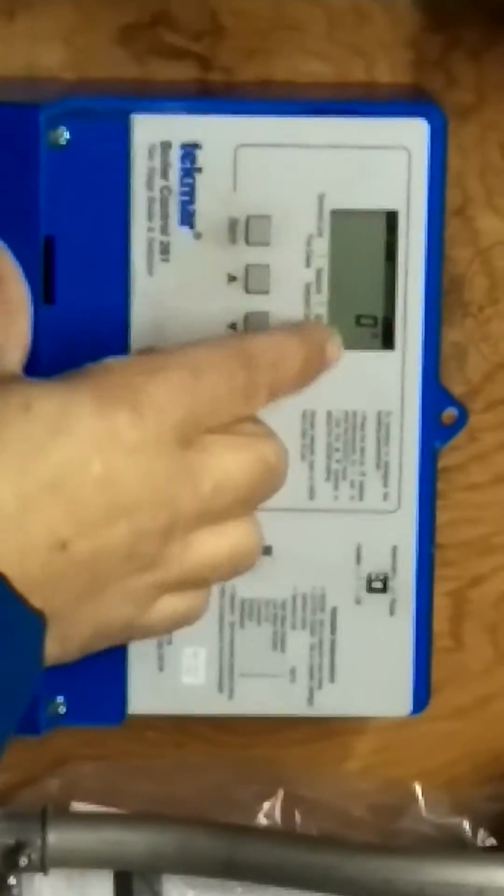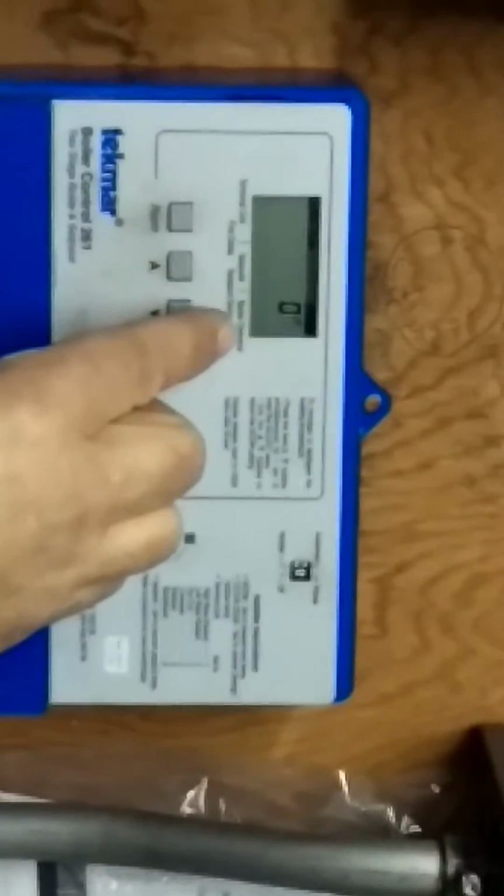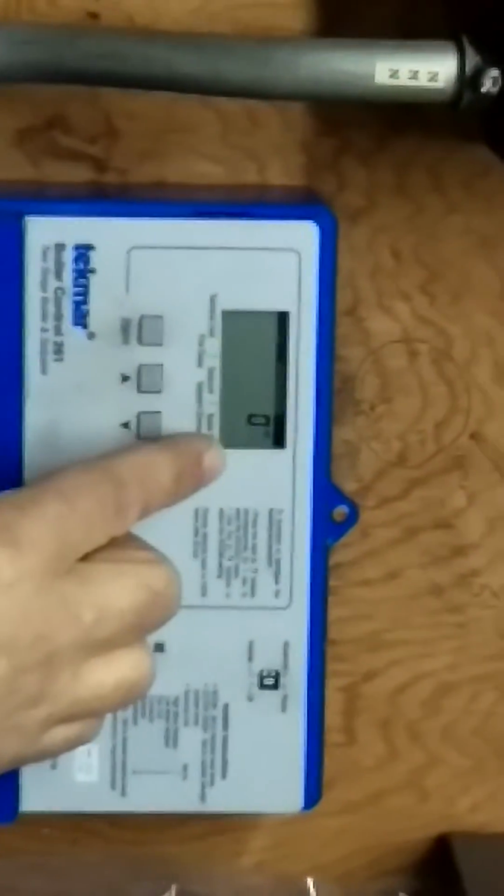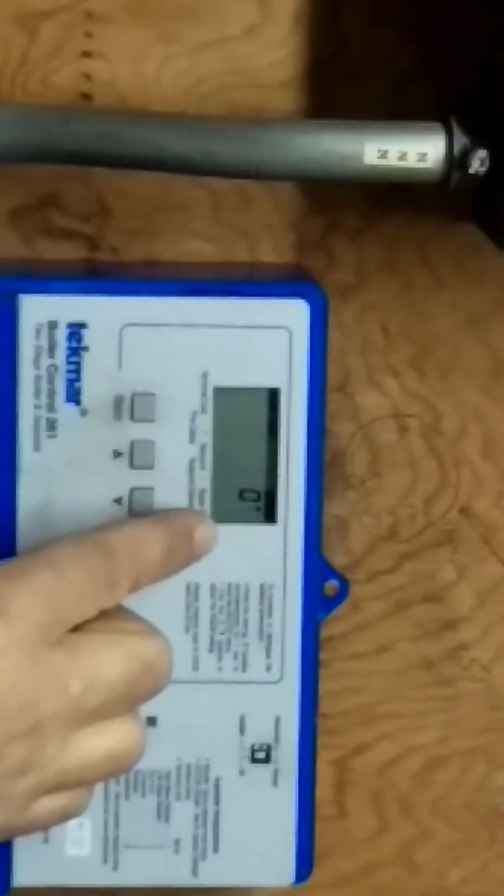The next one, outdoor design, OUT design. I like to put them at 0 Fahrenheit. The next one is basically whether we're using convector or radiator. It's radiator in here, isn't it? You've got cast iron radiators, don't you? Some of them, yeah.